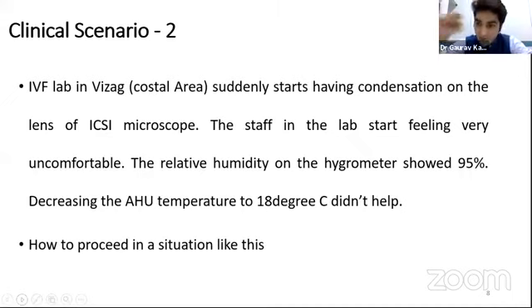You can have fungal growth, corrosion on the instruments, and short circuits of the incubators or the wirings nearby. So for that, you should maintain a controlled humidity of 40 to 60%.